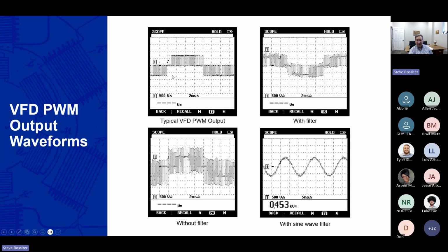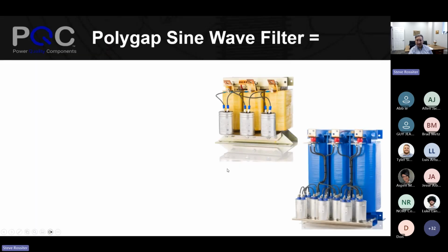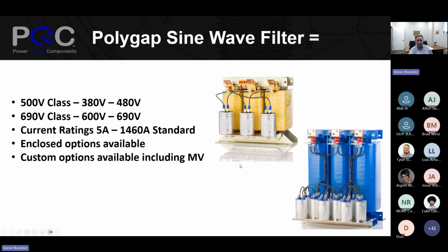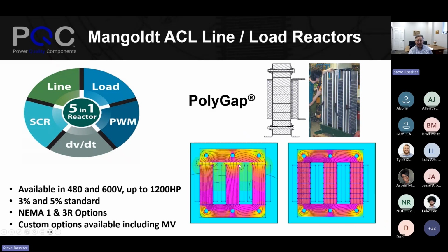And here are some examples. Here's the waveform. Here's what that looks like when you start seeing reflected wave. You can measure that. Here's what it looks like if you put in simple reactors or a little bit more sophisticated DVDT filters. And I talked earlier about submersible pumps. At some point, you just have to have a sine wave, and so here's a sine wave filter. Example of DVDT filters and reactors. There are different levels of quality with reactors and where they can operate, and flux density, and polygap or distributed air gap is one of the things that we talk about. If there's an interest in going to that detail, we can talk about that.